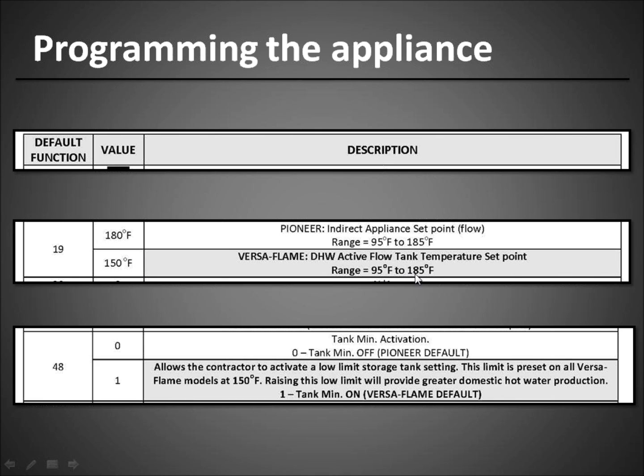The Pioneer, you can do the same thing also. To activate those on either appliance, obviously on the Flame, we activate the low limit by setting number 48 to 1. And in the Pioneer, we turn it off because we don't need to set a minimum. But if your contractors want to have a minimum for some reason on the Pioneer, that's an additional feature that we've added.